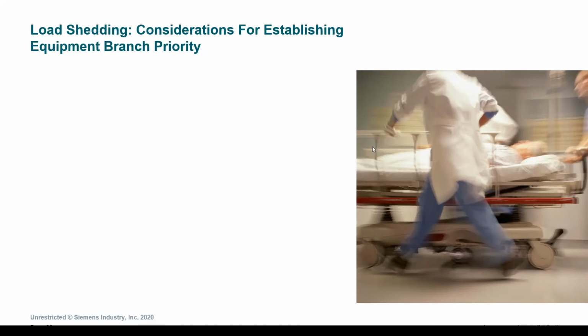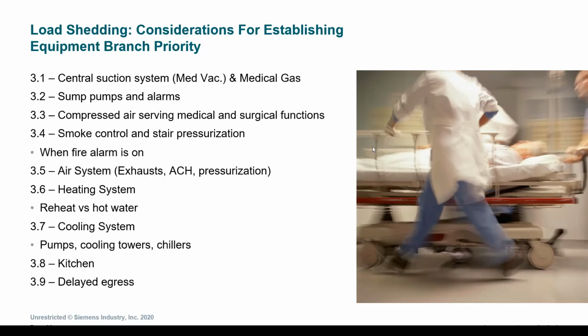Finally, when we look at the equipment branch priority, we again look at it as spaces or equipment that serves a higher level of acuity. First, starting with anything associated with a medical vacuum or medical gas. Obviously, this would be directly associated with the patient spaces, followed by any sump pumps or alarm. And then next proposed is 3.3. We get into any of the compressed air serving equipment or surgical functions like cleaning. And then this gets into smoke control and stair pressurization, followed by the mechanical system.